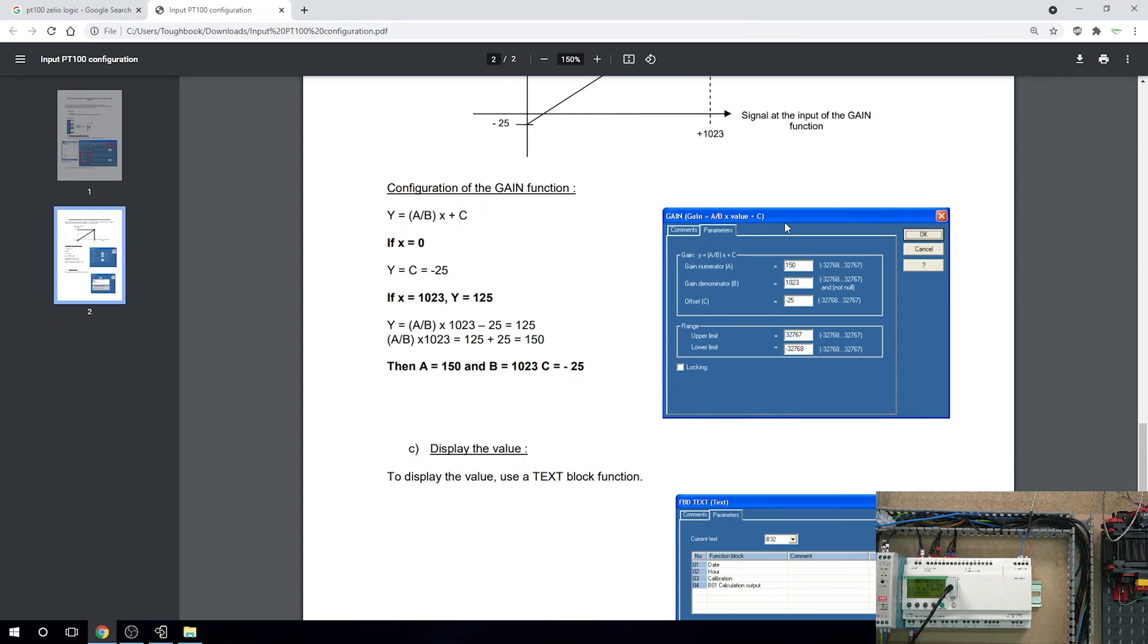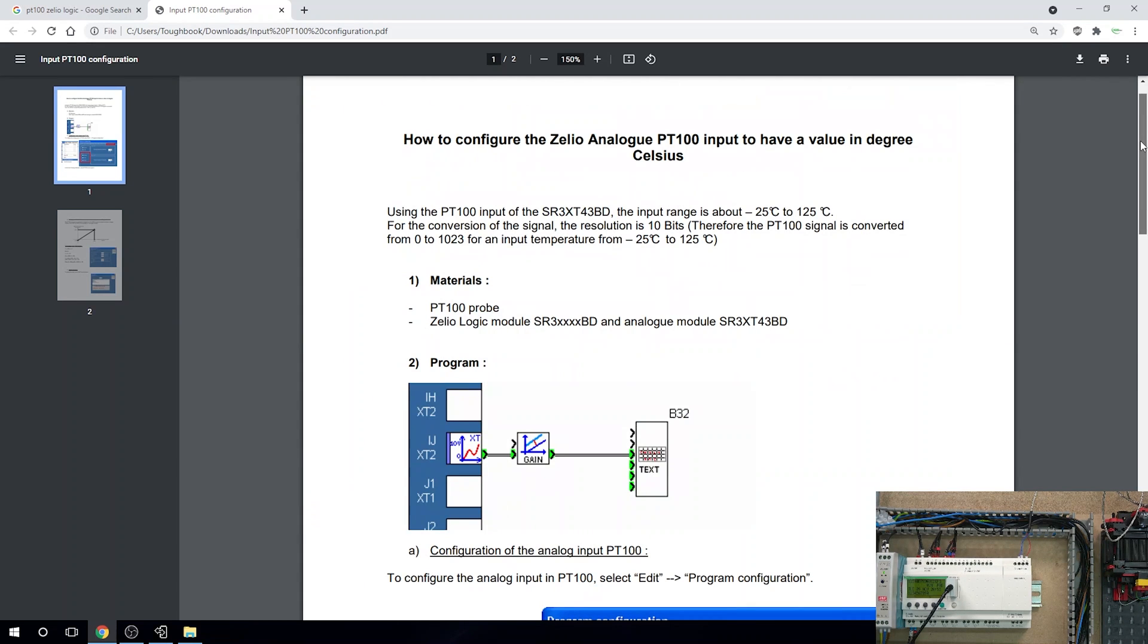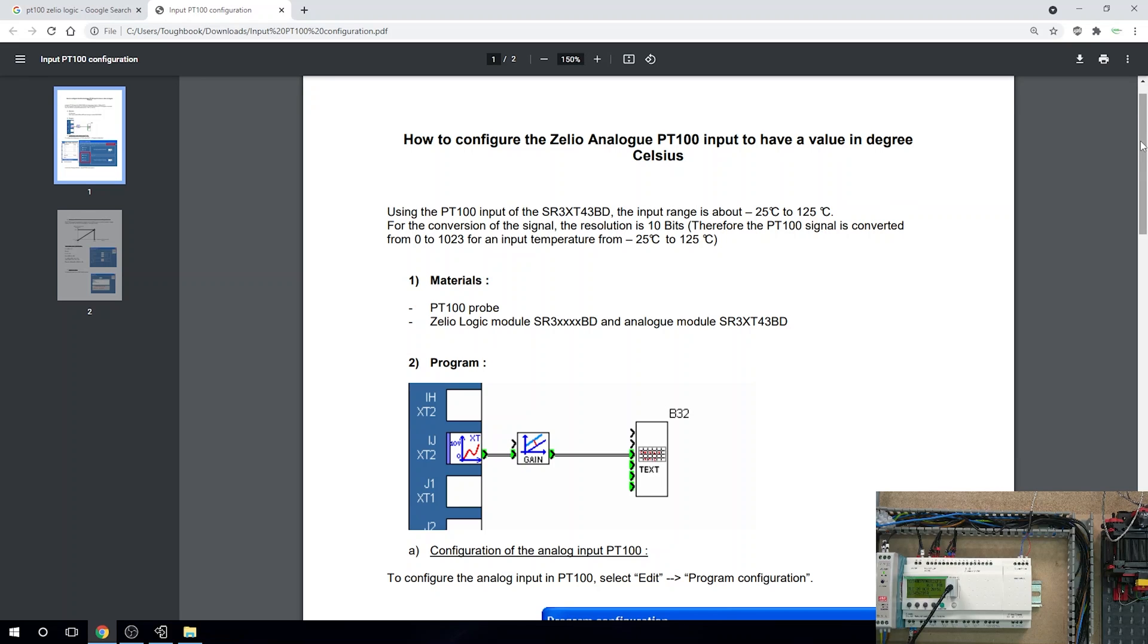It pretty much tells you exactly what you need to do to get this working properly. As you can see, using PT100 input of this particular module that we're working on, its input range is about minus 25 to 125°C. If you have a different temperature range, you might have to consider different equipment. For the conversion of the signal, the resolution is 10 bits.